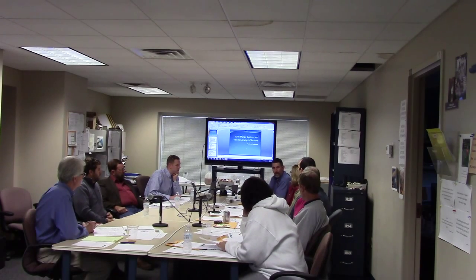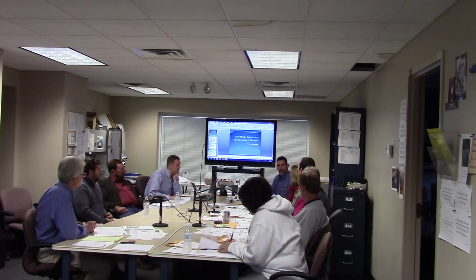The SCADA acronym stands for Supervisory Control and Data Acquisition. That's what we're looking to do—get up-to-the-minute reports of what's going on at the substation, whereas now I have no idea unless I walk out there and take a reading. I could punch it up on the computer and see my megawatt load on each circuit, the amps per phase, the power factor. The system will tell me if a breaker trips and send a text or email to our linemen saying what happened at the substation. Right now we don't know unless we get a call from a customer saying they're out of power. The lineman will probably get notified before the customer could even contact them.